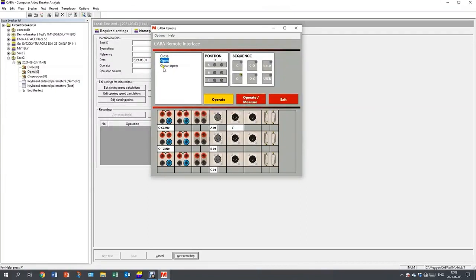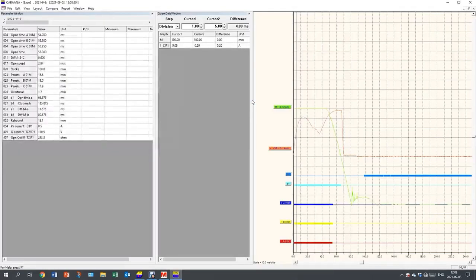I continue with the open operation. And again, don't forget to press control. And it's going to be a bang. I get the timings, the auxiliary contact timing, the coil current, and the motion. We get a timing result of about 55 milliseconds, and the current max is 0.5 amps. And we close and finish.